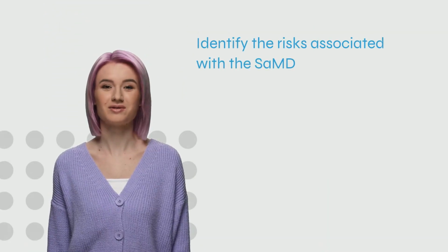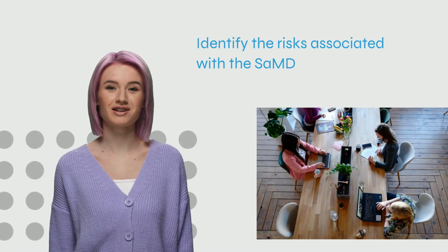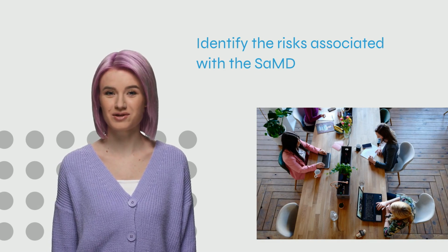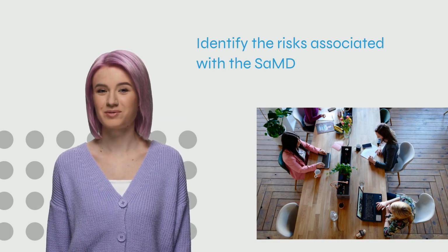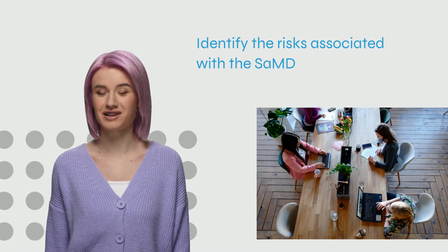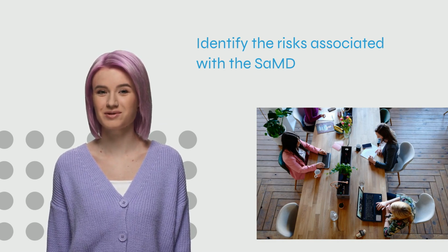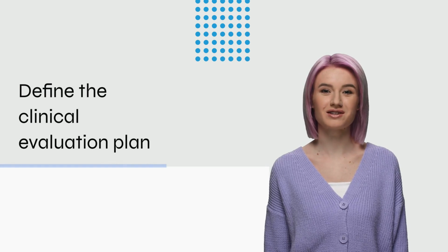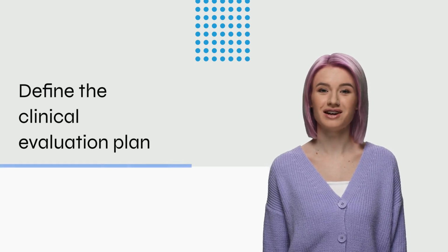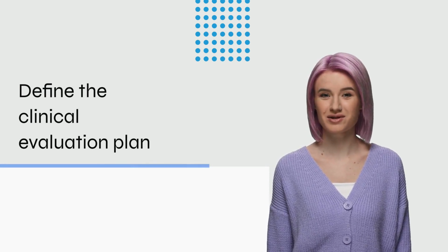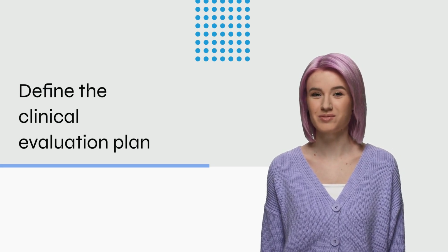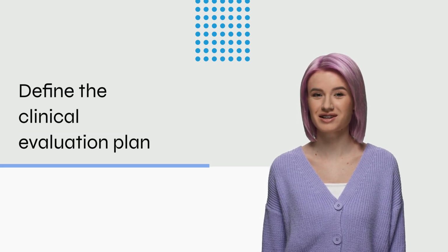The third step is to identify the risks associated with the SaMD. This involves assessing the potential risks associated with the use of the software. Some examples would be misdiagnosis, inaccurate data analysis, or incorrect treatment recommendations. After identifying the intended use, clinical benefits, and risks associated with the SaMD, the next step is to define the clinical evaluation plan. The plan outlines the methodology for evaluating the clinical performance of the software and identifying any potential risks.